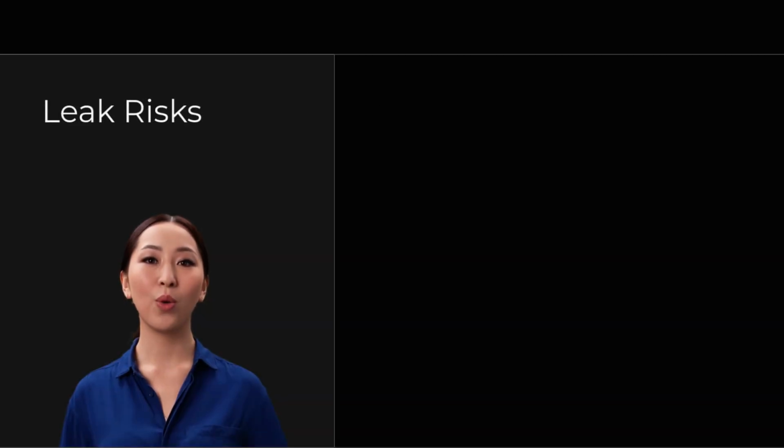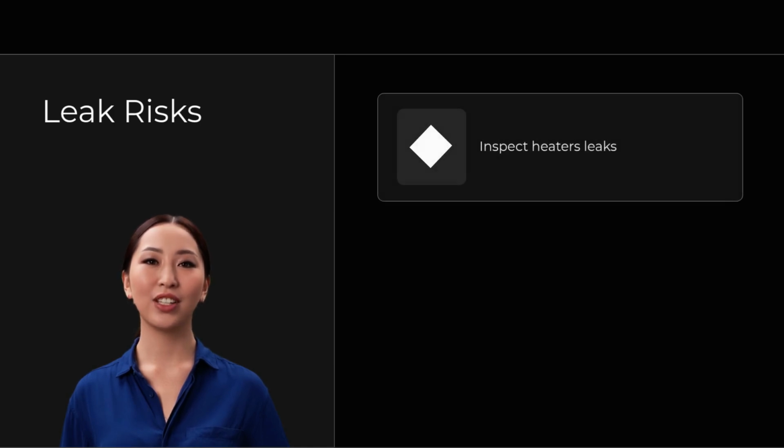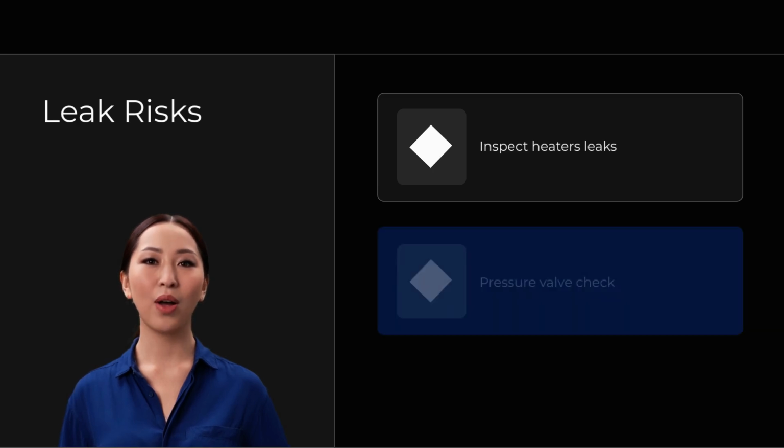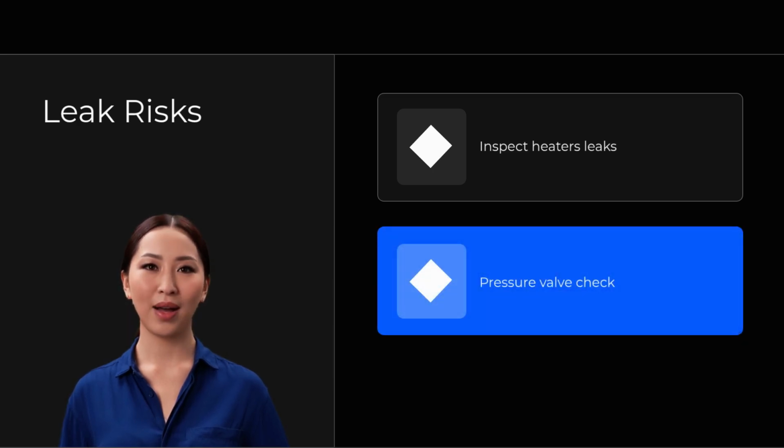Teams should also inspect water heaters for corrosion, leaks, sediment buildup, and pressure valve issues. Shut-off valves need to work so water can be isolated quickly in an emergency, and findings should be recorded during the inspection for better accuracy and accountability. Preventive checks help uncover hidden leaks, sewer backups, low pressure, faulty valves, and water heater sediment early.